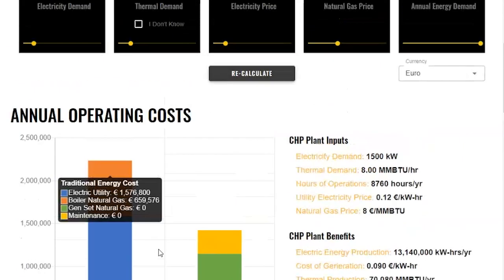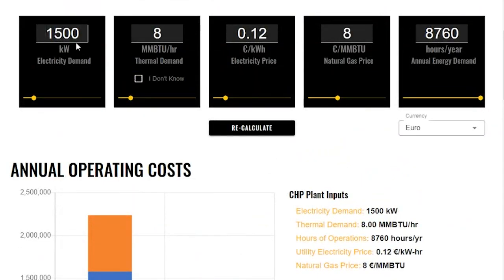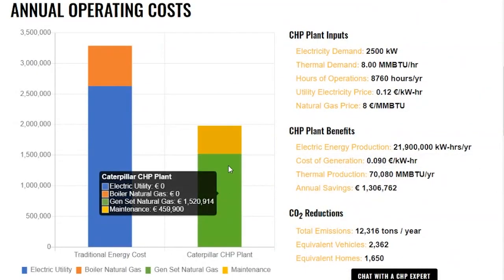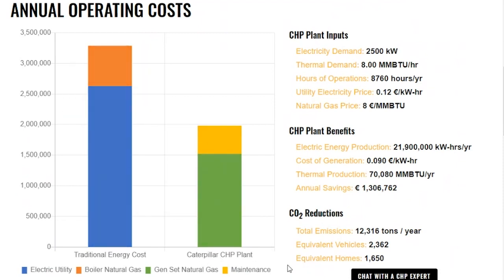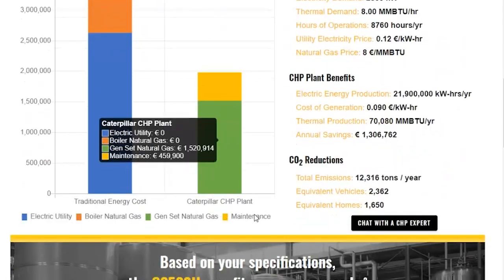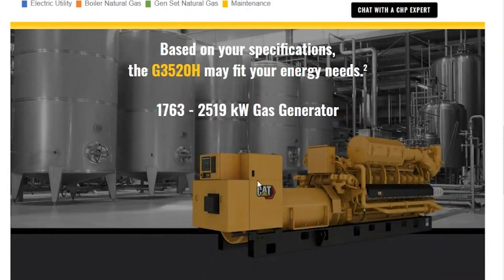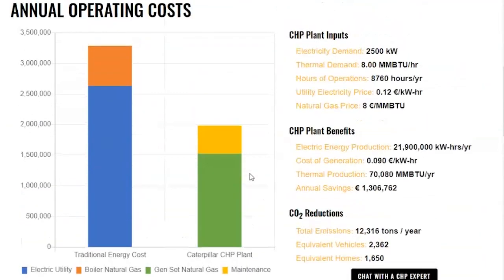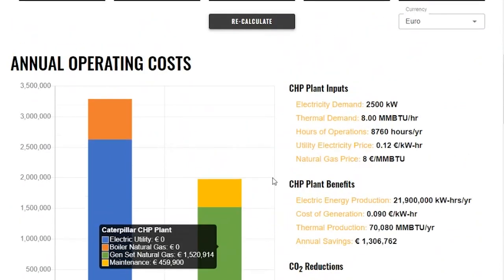So let's go back up and choose a larger Caterpillar genset — I'm going to choose a 2,500 kW genset instead to see if that will meet it. It turns out that the 2,500 kW genset can meet my total energy demands. If you scroll down to the bottom, you can also see that a G3520H is the right size genset for this application.